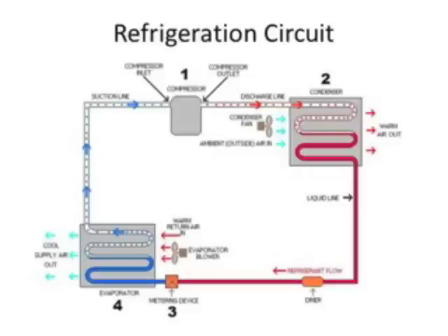So here's the basic refrigeration circuit laid out in a loop. Makes it a little bit easier for us to see all the components and how it works in a continuous cycle. Basically, the basic components we're going to go over is just the bare bones. We've got the compressor, the condenser coil, the liquid line filter dryer, the metering device, and the evaporator coil. Basically, that's all you need to create a refrigerant circuit.